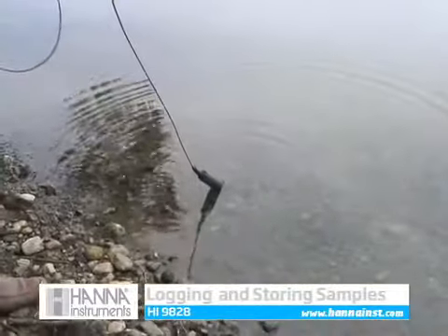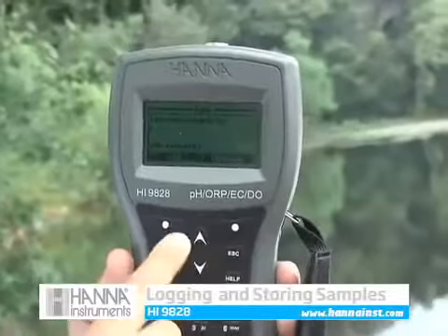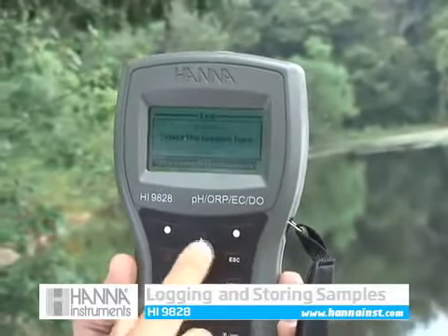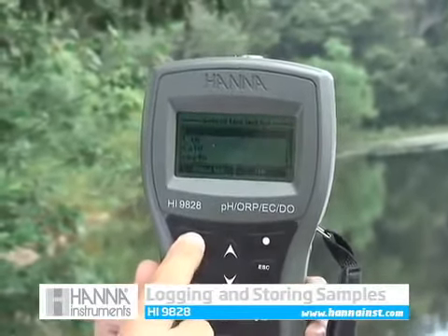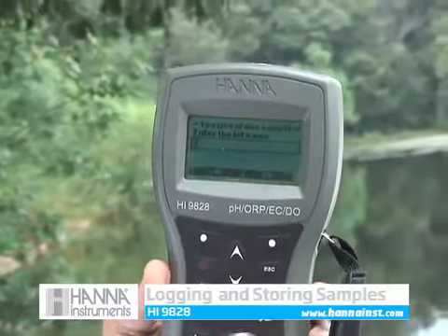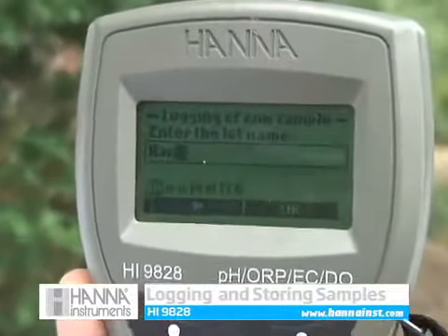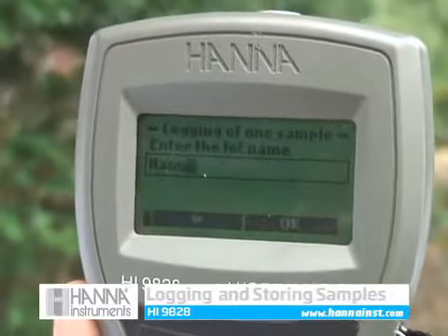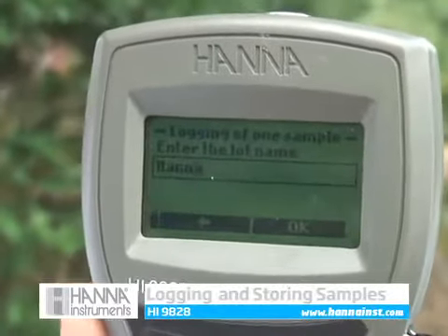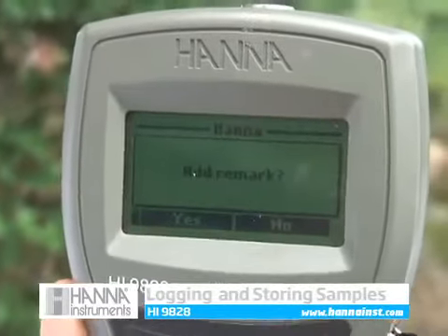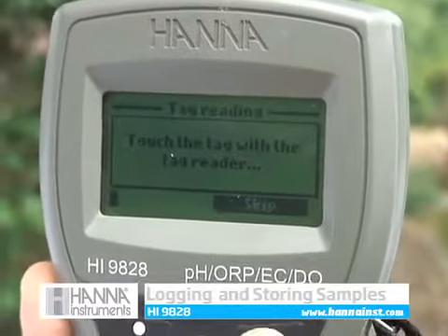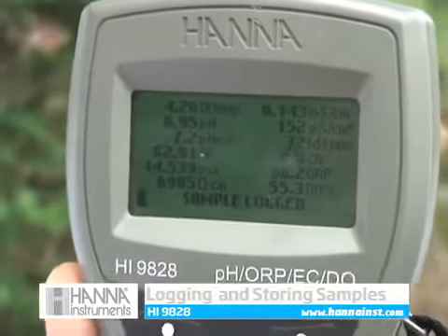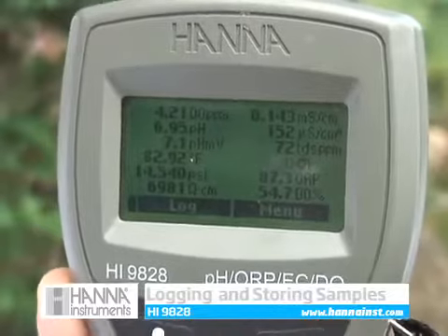The HI9828 has the ability to store up to 60,000 samples in 100 different lots, 48,000 if GPS is enabled. From the measurement mode, press the log key to store enabled readings into the default lot or custom name lot as shown. Remarks may be added to your log data as well as location information from the Fast Tracker Tag ID system or GPS. Continuous logging can also be chosen with logging intervals between 1 second and 3 hours.